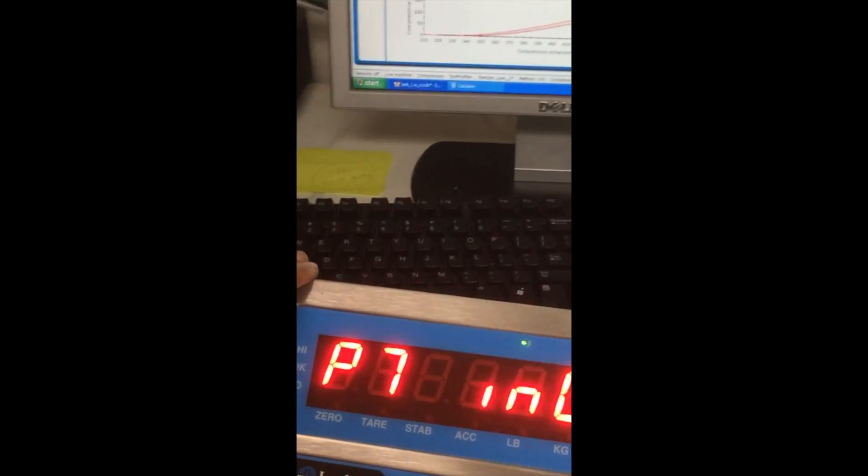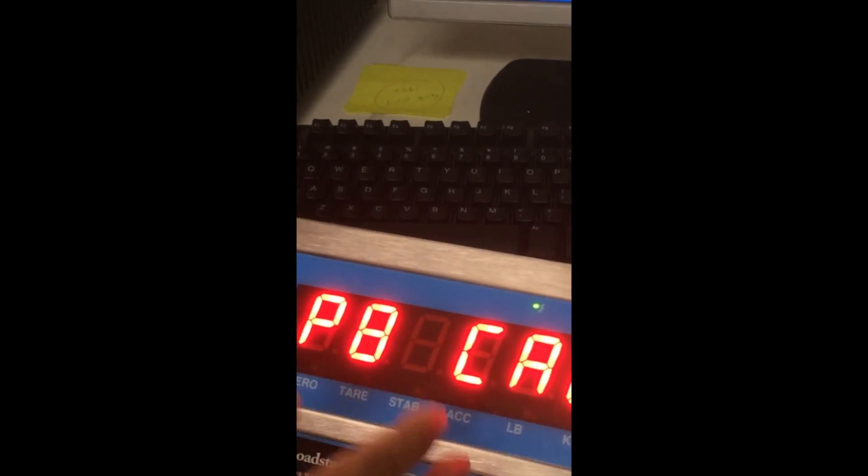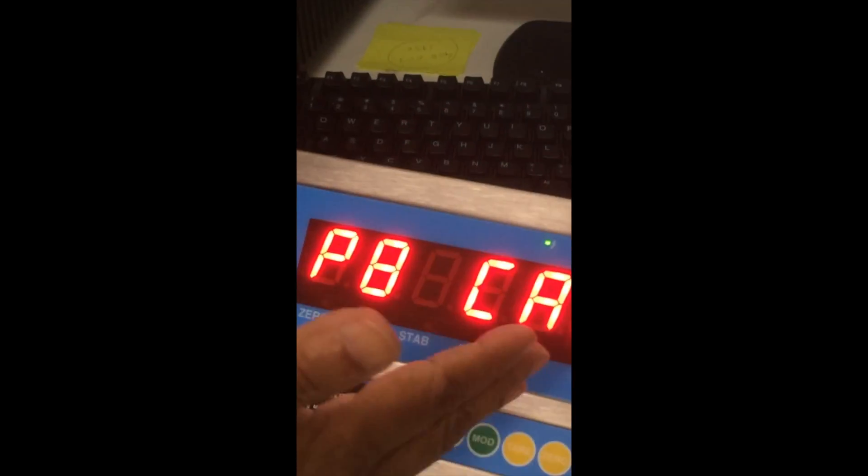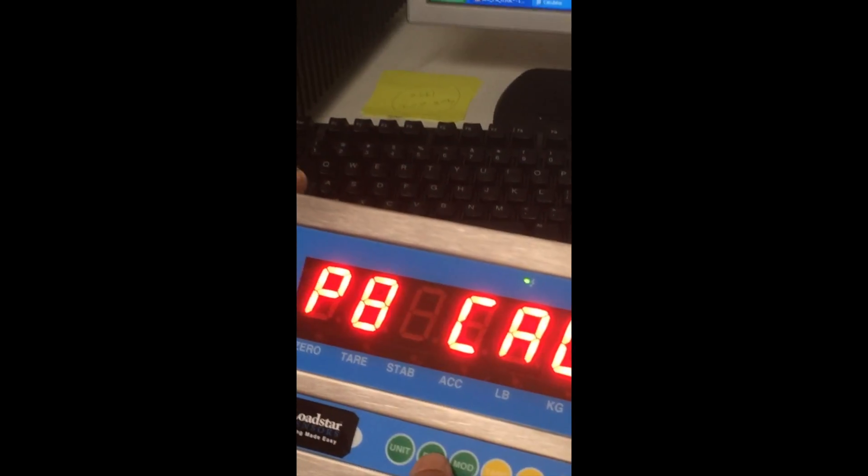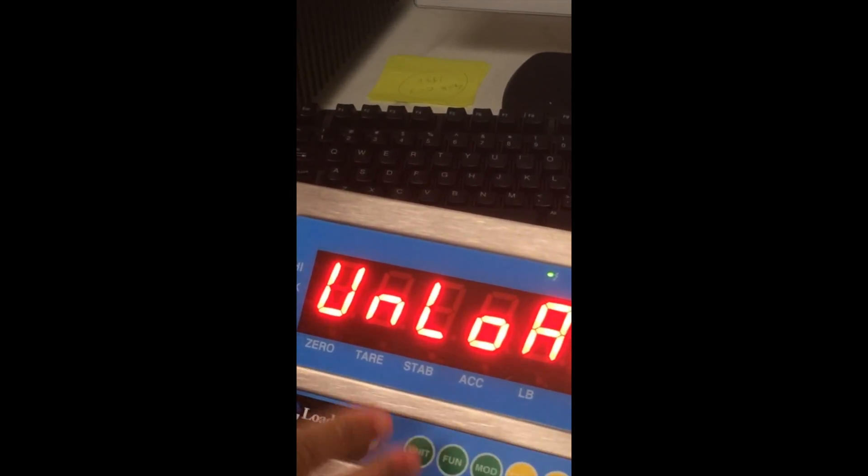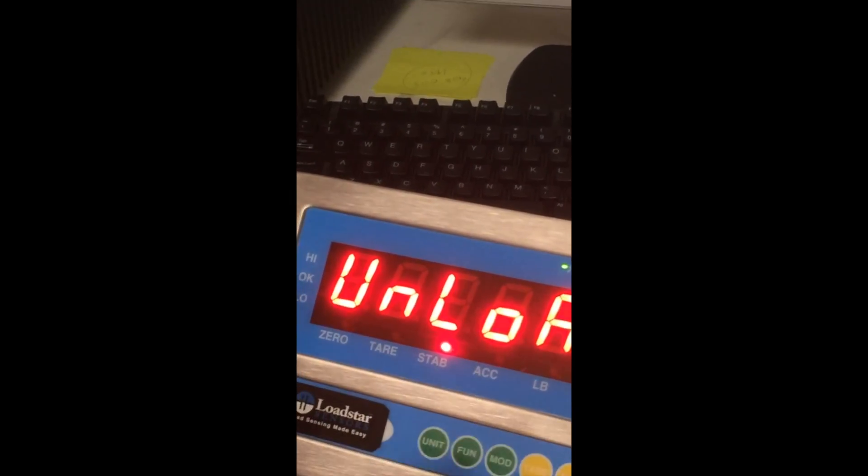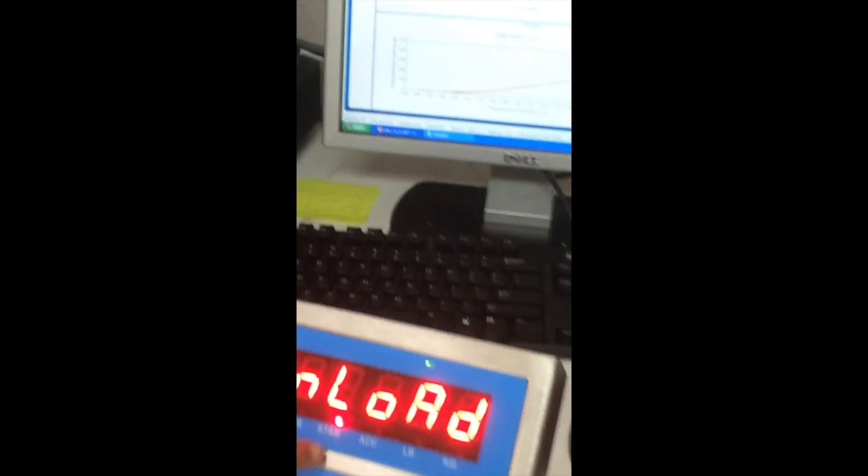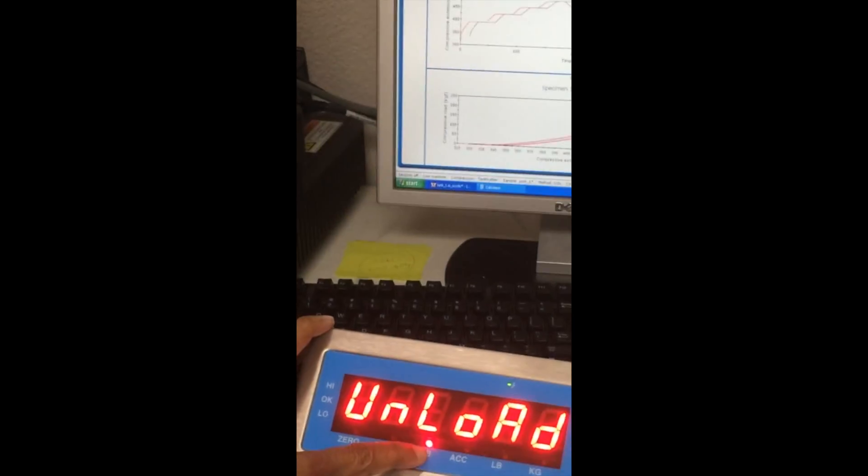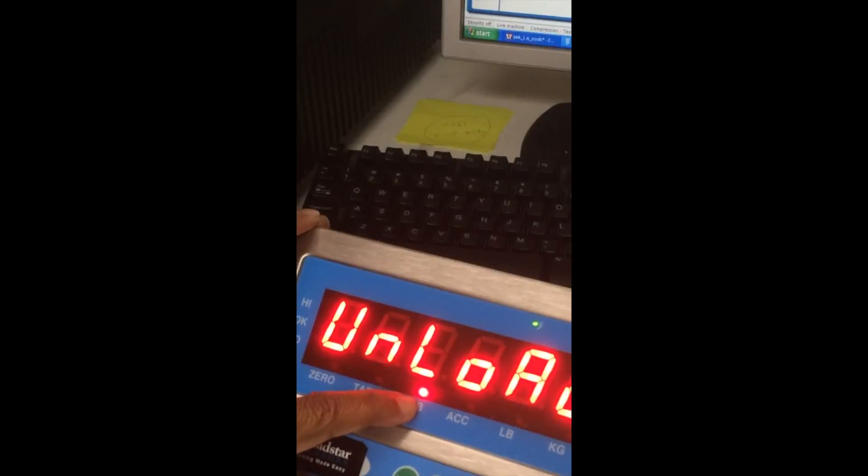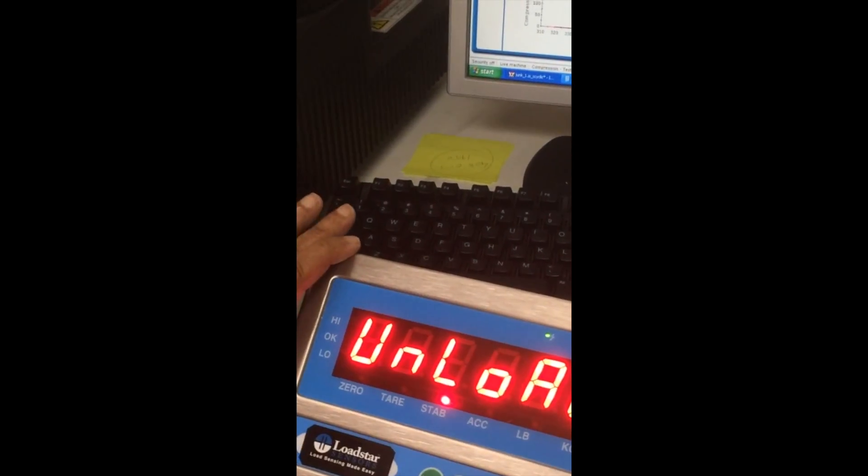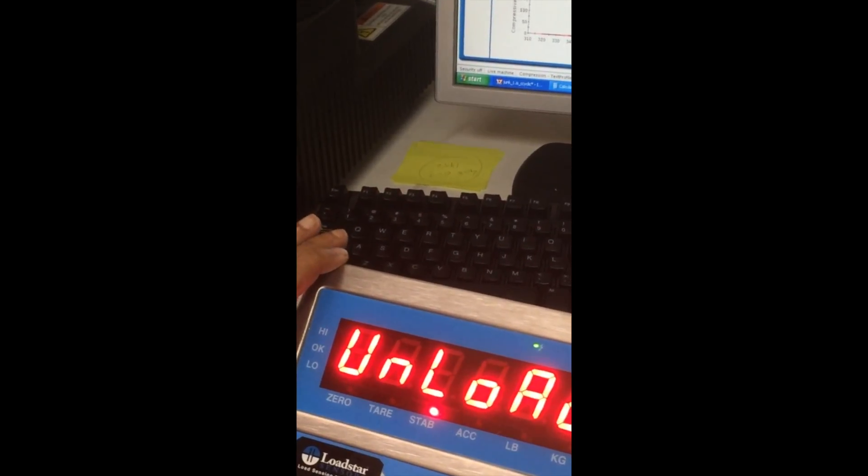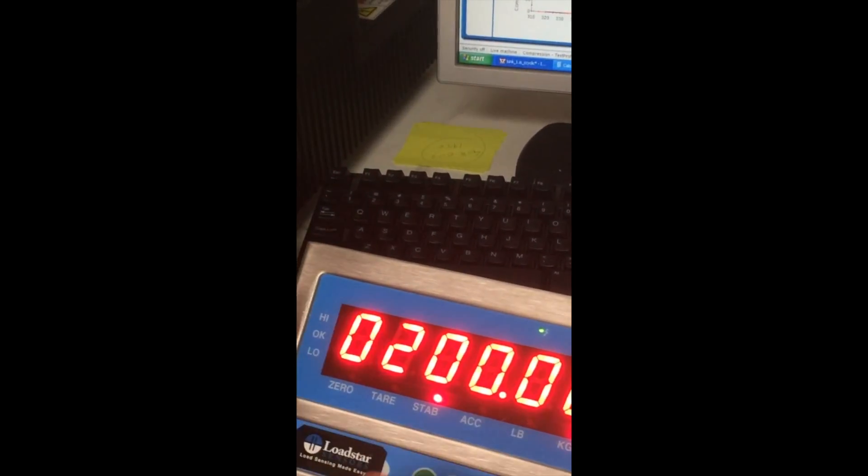Now go up to Cal. This is the real Cal. I am going to calibrate. Function. So it says unload. So make sure there is no load on the load cell. And you should see that this is stable. This should be steady, not blinking. So it's steady, no load. Press the function key. Accept it.